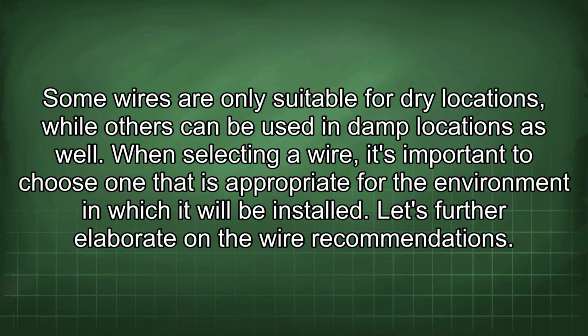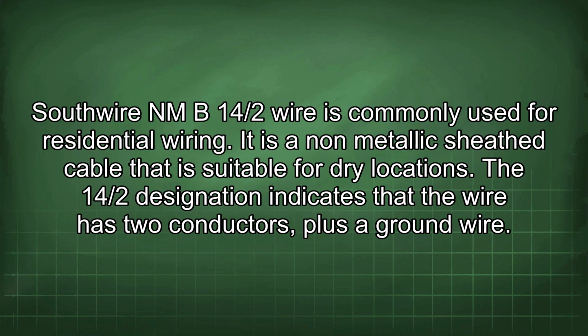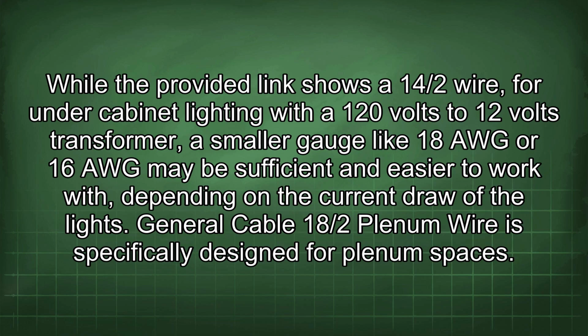Let's further elaborate on the wire recommendations. Southwire NM-B 14/2 wire is commonly used for residential wiring. It is a non-metallic sheath cable that is suitable for dry locations. The 14/2 designation indicates that the wire has two conductors plus a ground wire, while the provided link shows a 14/2 wire for under-cabinet lighting with a 120 volts to 12 volts transformer. A smaller gauge like 18 AWG or 16 AWG may be sufficient and easier to work with, depending on the current draw of the lights.